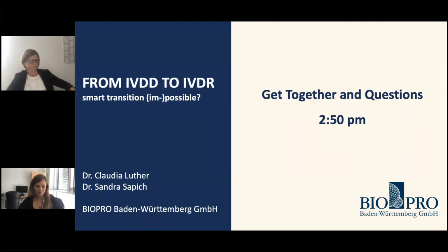And we need to add that the IVDR differentiates between point of care, which the IVDD didn't. There we just had the difference between professional use and self-testing, and now we have the different levels: professional use, point of need, point of care, and lay user. There are different or particular requirements for usability for point of care testing under Annex 1. Exactly. Okay, if there are no more questions.